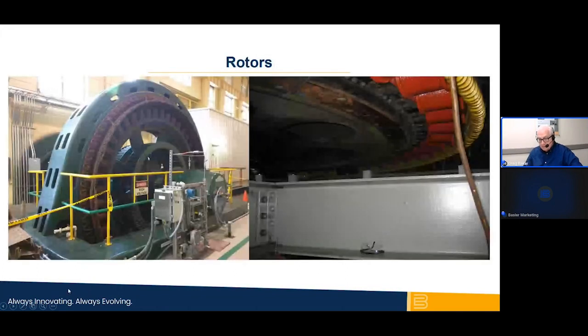Smaller generators are cooled with air. Many are open loop, with ambient air drawn in and exhaust air returned to the ambient air space. Some air-cooled systems provide secondary cooling with heat exchangers to draw heat away from the machine. The temperature of the coolant is a variable that influences the maximum capacity of the synchronous machine. Next slide.